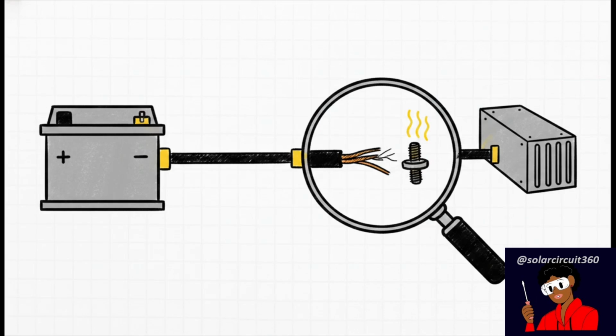Here's what you're looking for. If you see a major discrepancy between those two readings under load, like say your battery voltage stays pretty stable, but the voltage at the inverter just tanks, boom, you've found your hidden resistance. That tells you your battery is fine, your inverter is fine, and the problem is literally sitting in the space right between them. You've got to meticulously check for loose hardware, heat damage, melted insulation, or double check that your cable gauge is actually thick enough for the massive current your inverter demands.